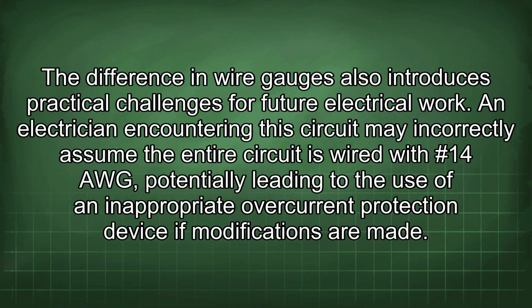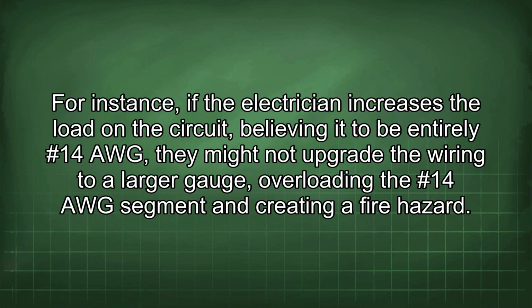The difference in wire gauges also introduces practical challenges for future electrical work. An electrician encountering this circuit may incorrectly assume the entire circuit is wired with #14 AWG, potentially leading to the use of an inappropriate overcurrent protection device if modifications are made. For instance, if the electrician increases the load in the circuit, believing it to be entirely #14 AWG, they might not upgrade the wiring to a larger gauge, overloading the #14 AWG segment and creating a fire hazard.